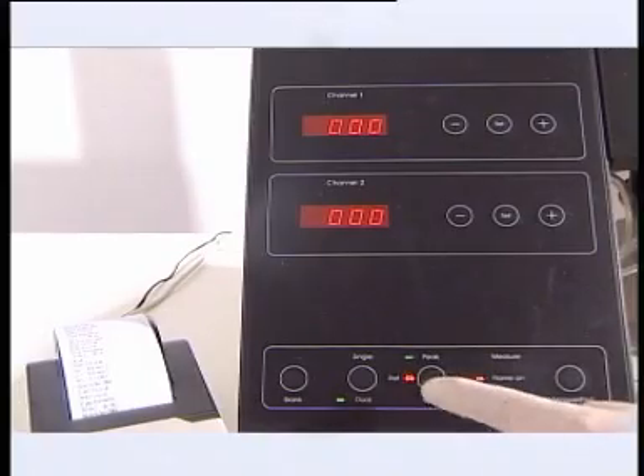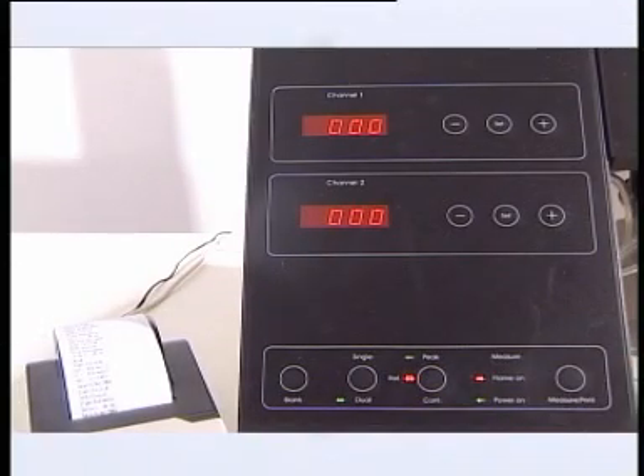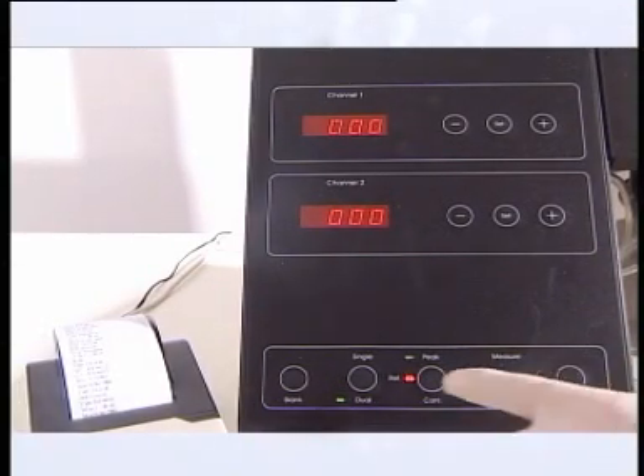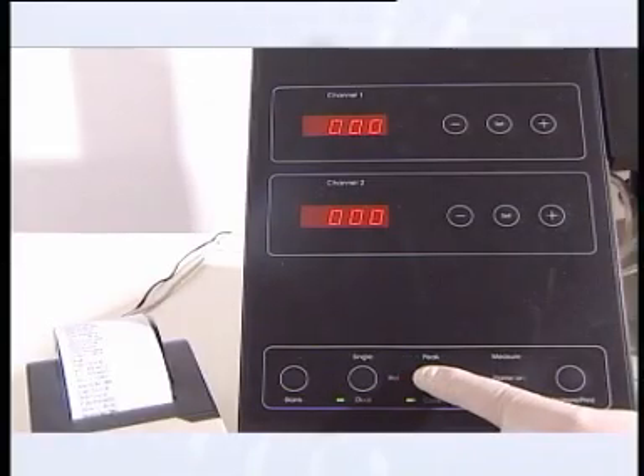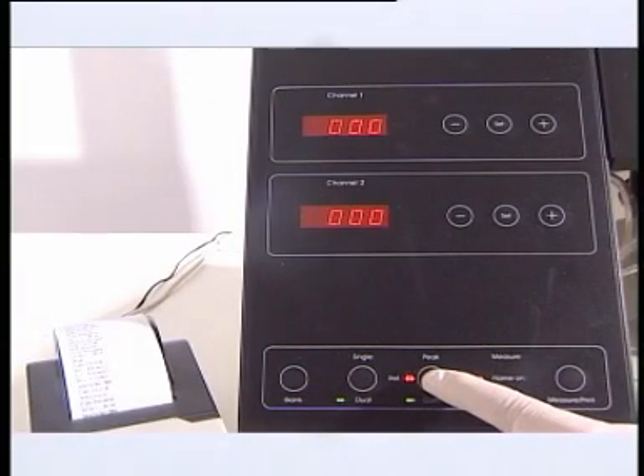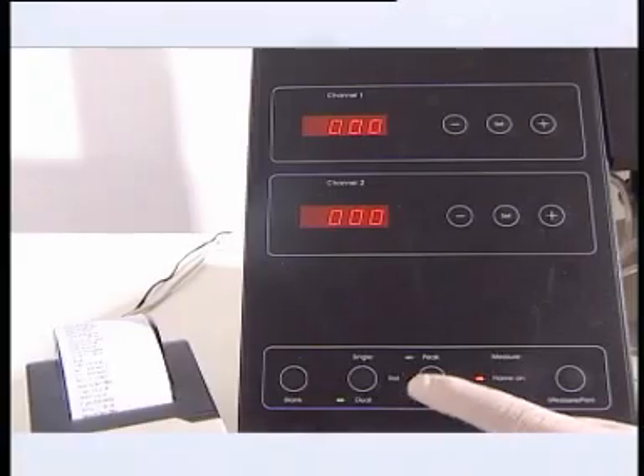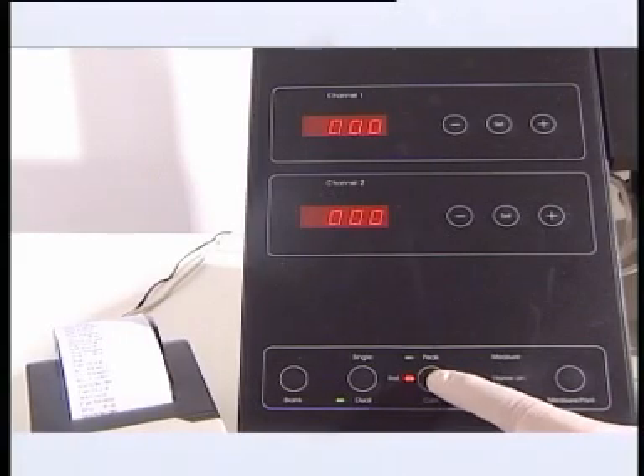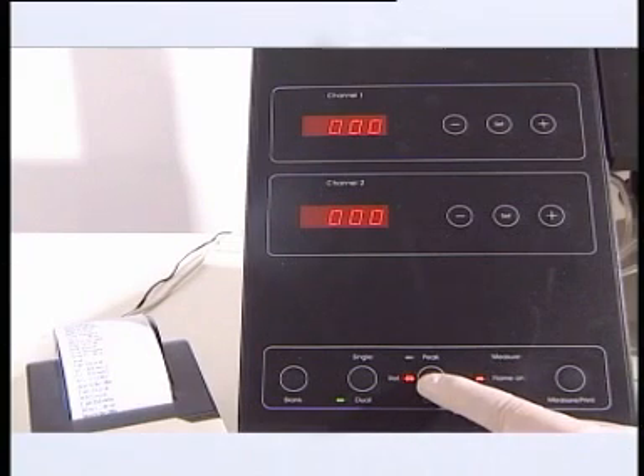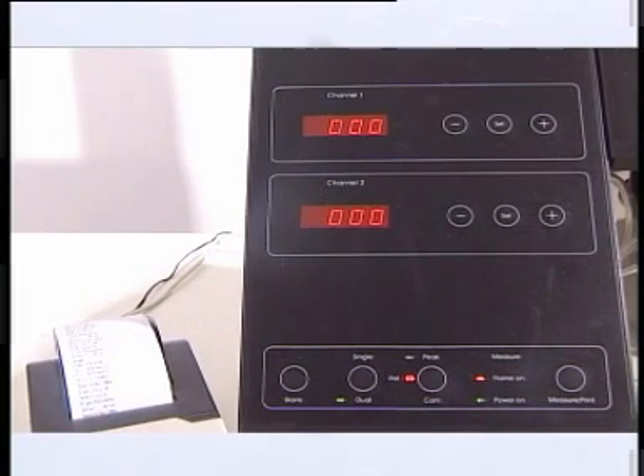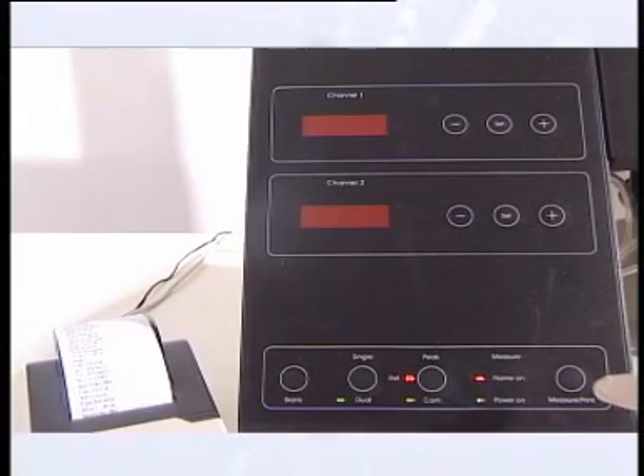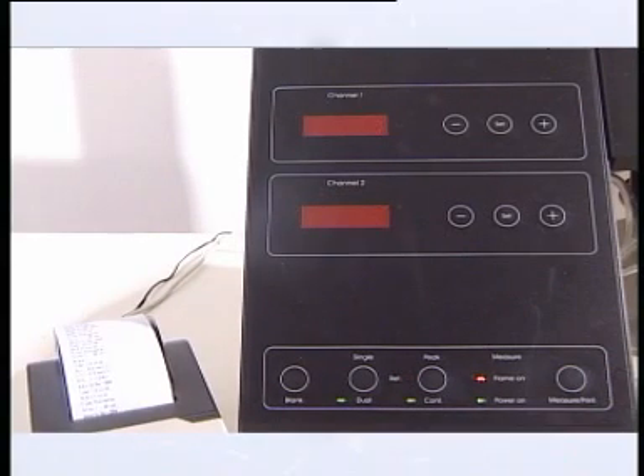The mode button selects between peak mode, where the Model 420 identifies and captures the stable value, and continuous measurement, used primarily when the Model 420 is used as a detector in a larger system. Ref is used when the lithium internal standard is in operation. Note that ref cannot be selected if lithium is being measured. The final button initiates a new measurement and sends a print signal when in continuous mode.